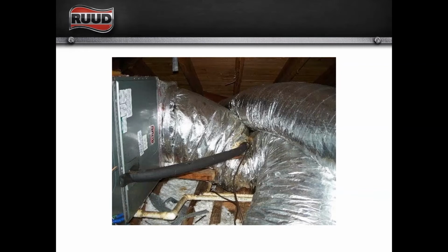So if you go to a job and you see something like this where you've got a piece of ductwork that is crushed, or like the previous one, you owe it to yourself and to your customer to fix that. Don't just leave it and say, hey, it's not my problem, because it's very possible that is one of the reasons that you're there, whether it's replacing a blower motor or the system's not keeping up or whatever, right? So we've got to identify these things and we've got to fix them.